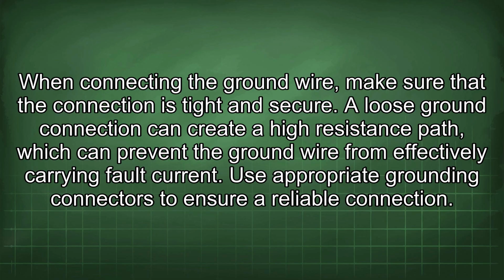When connecting the ground wire, make sure that the connection is tight and secure. A loose ground connection can create a high resistance path, which can prevent the ground wire from effectively carrying fault current. Use appropriate grounding connectors to ensure a reliable connection.